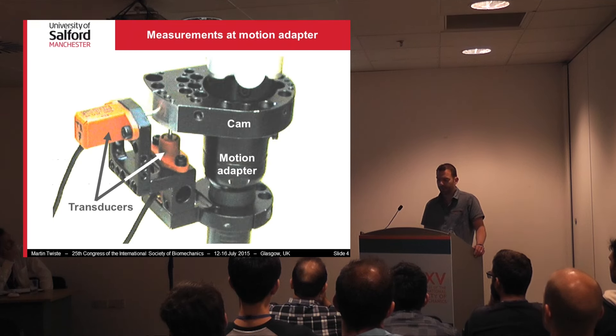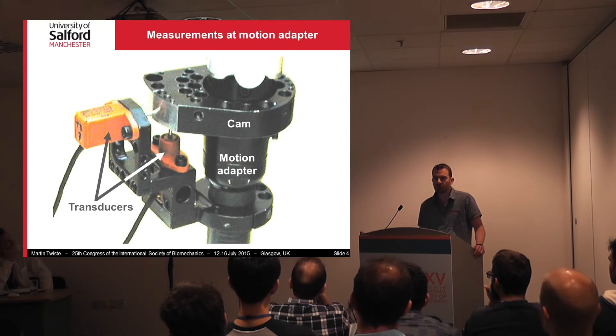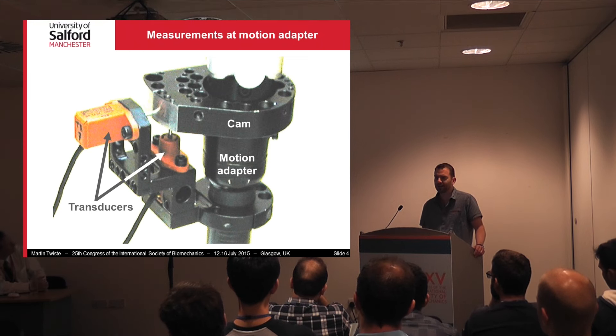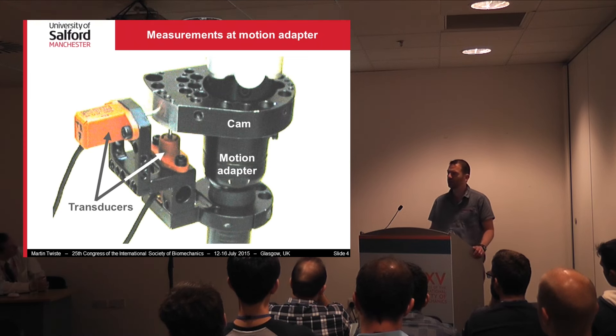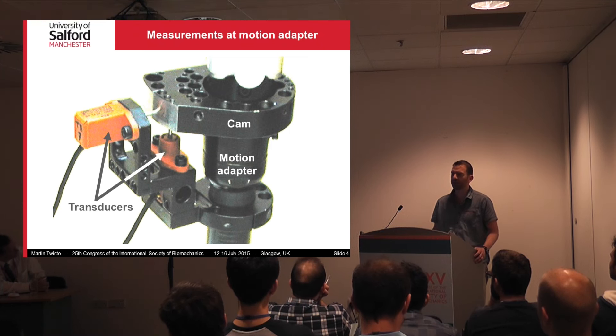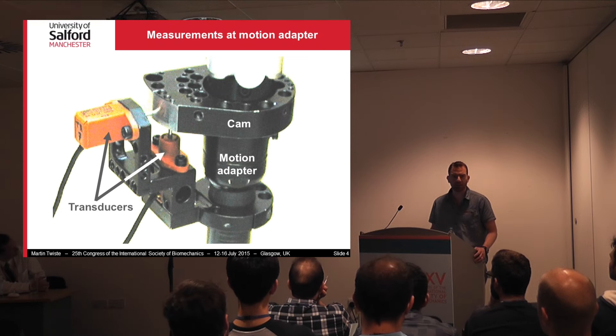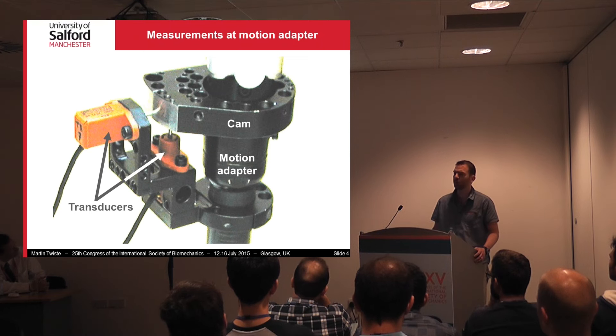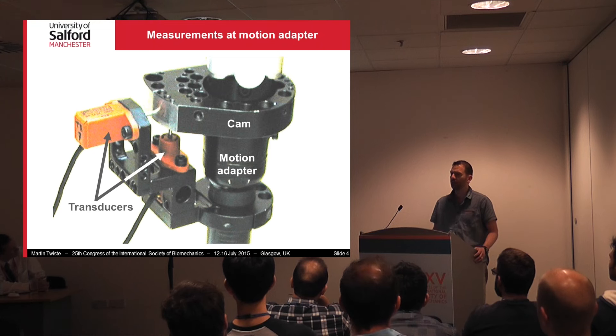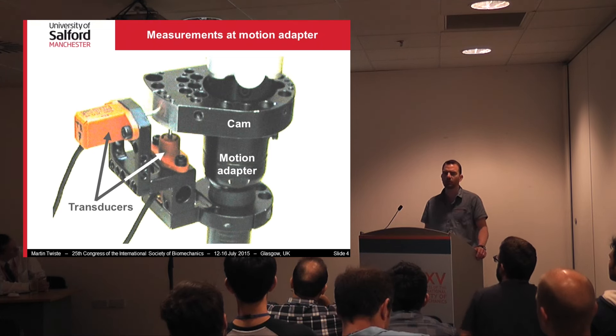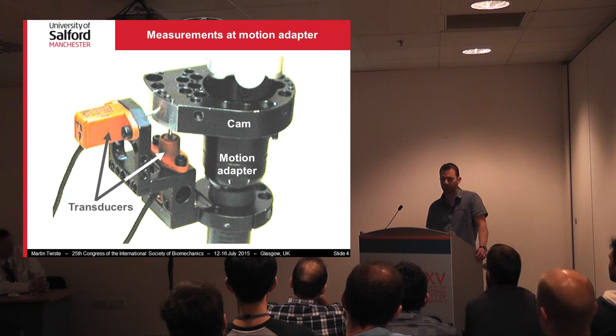To capture motion of the motion adapter, we designed a little device rather than using a camera system. We used a plate cam mounted around the motion adapter, working in conjunction with two linear displacement transducers — one mounted parallel to the longitudinal axis of the motion adapter, and one perpendicular to it.